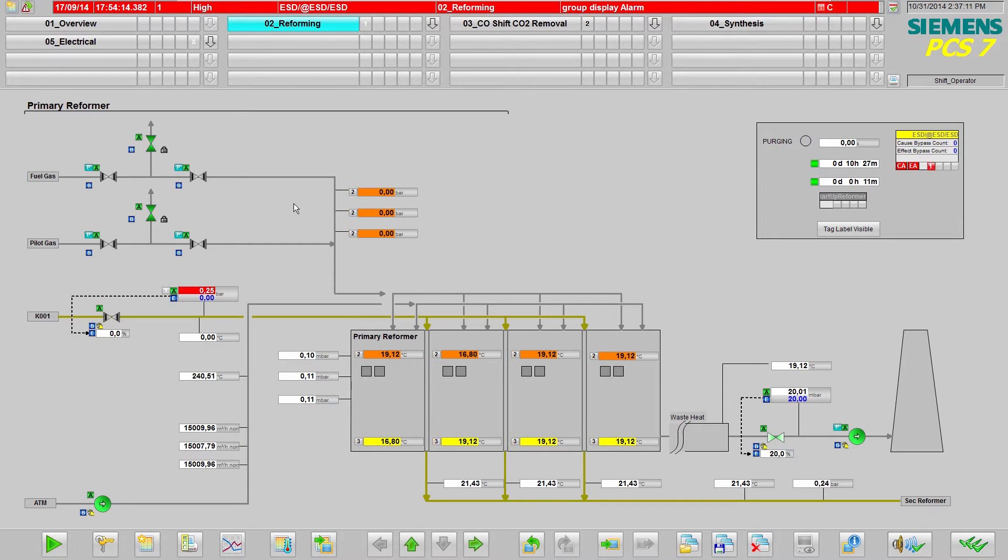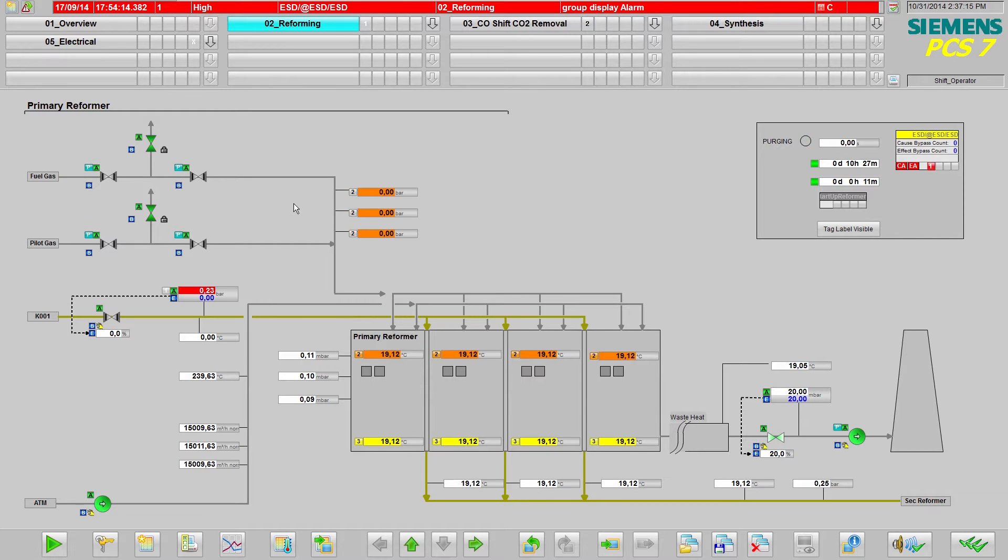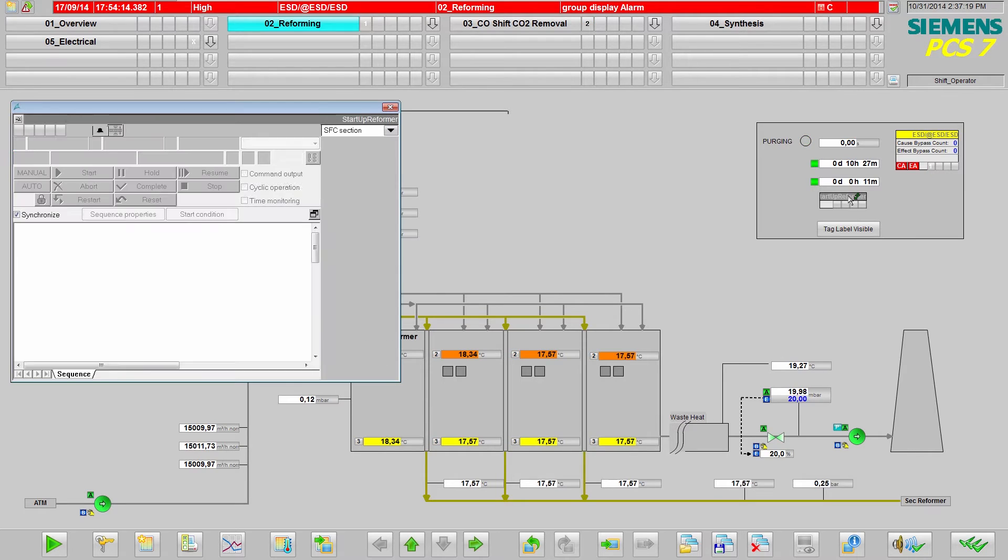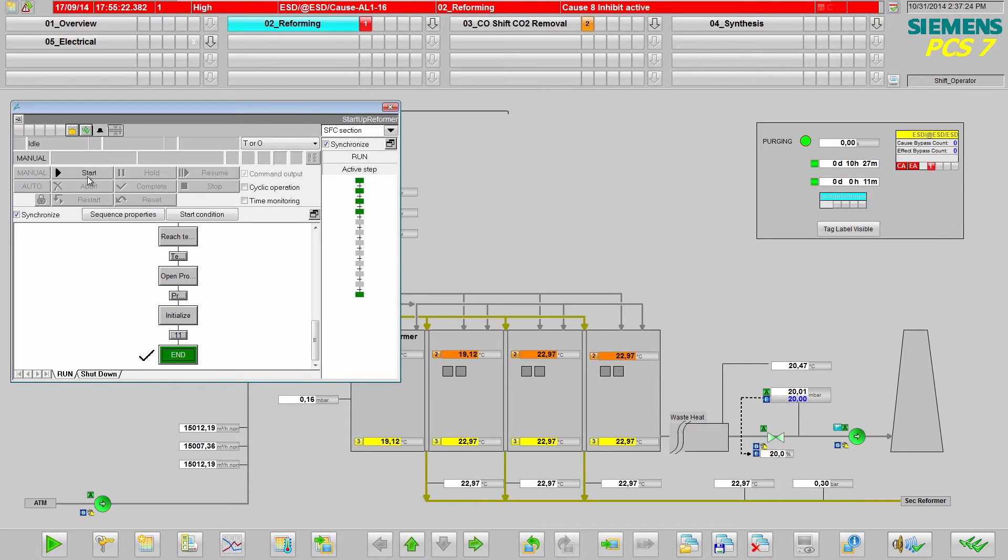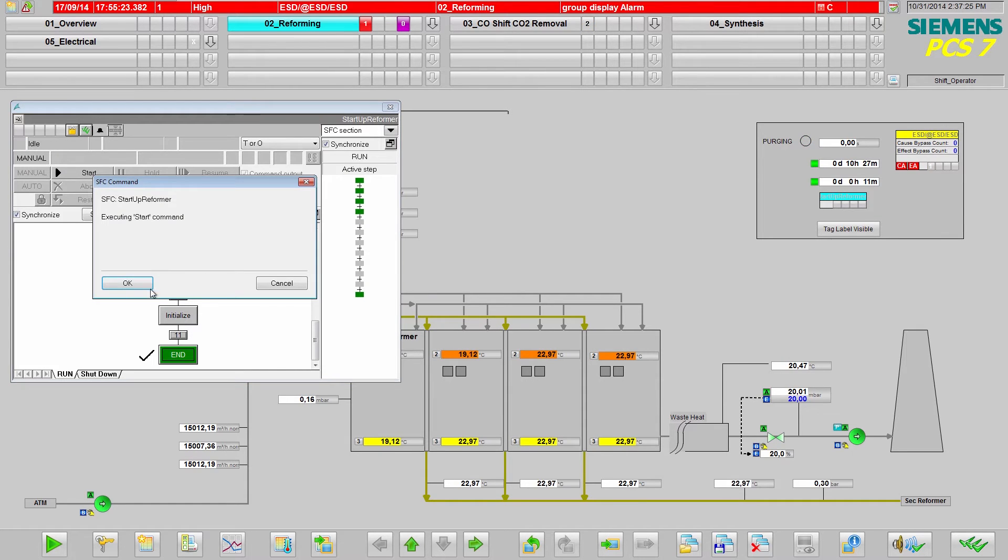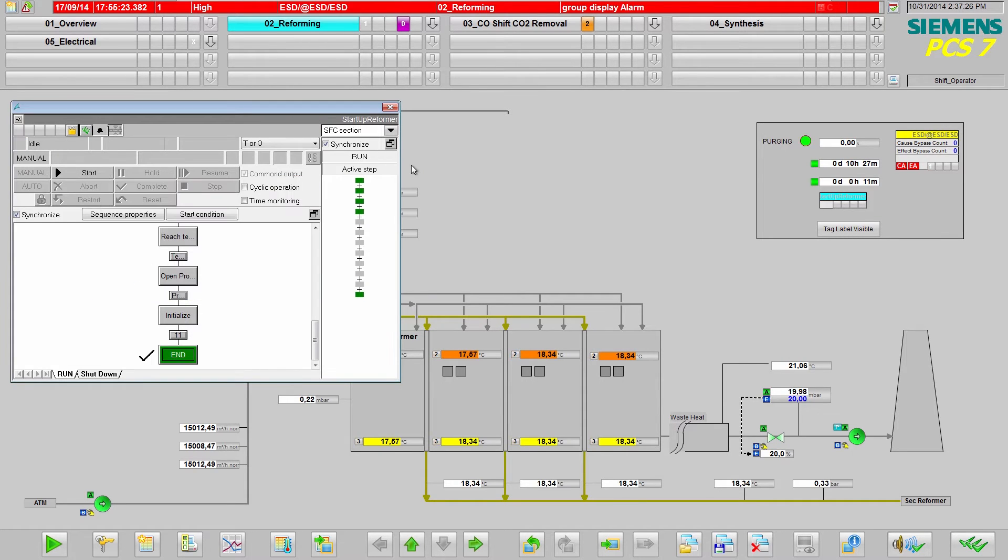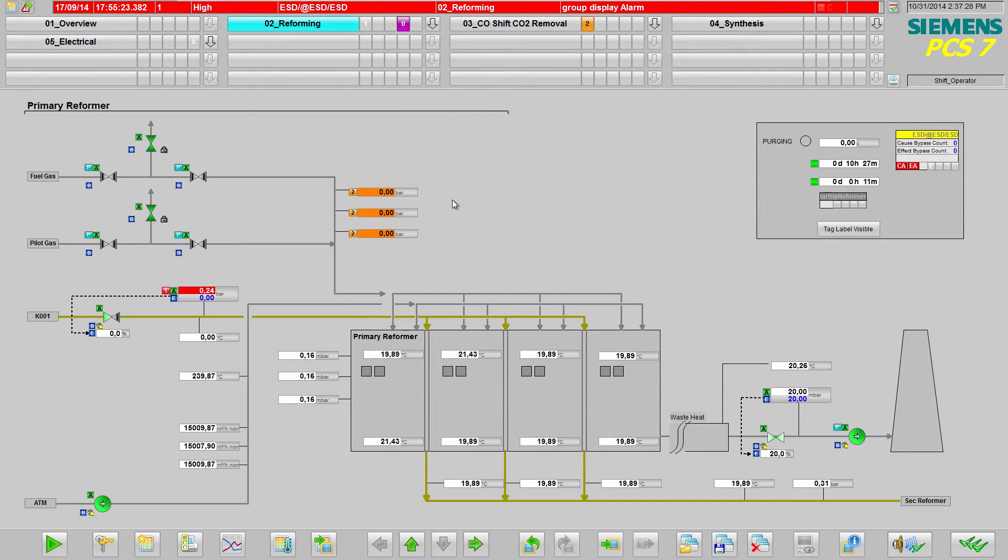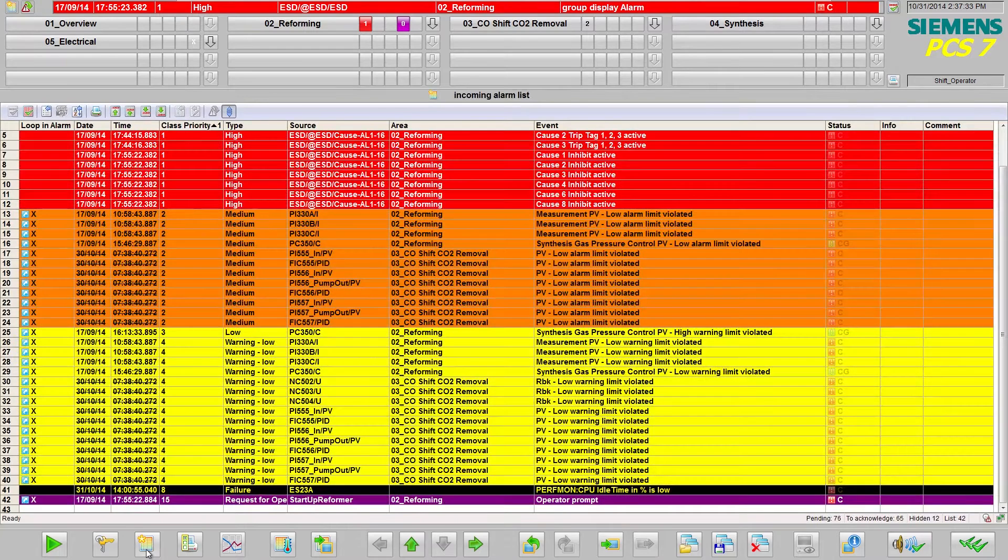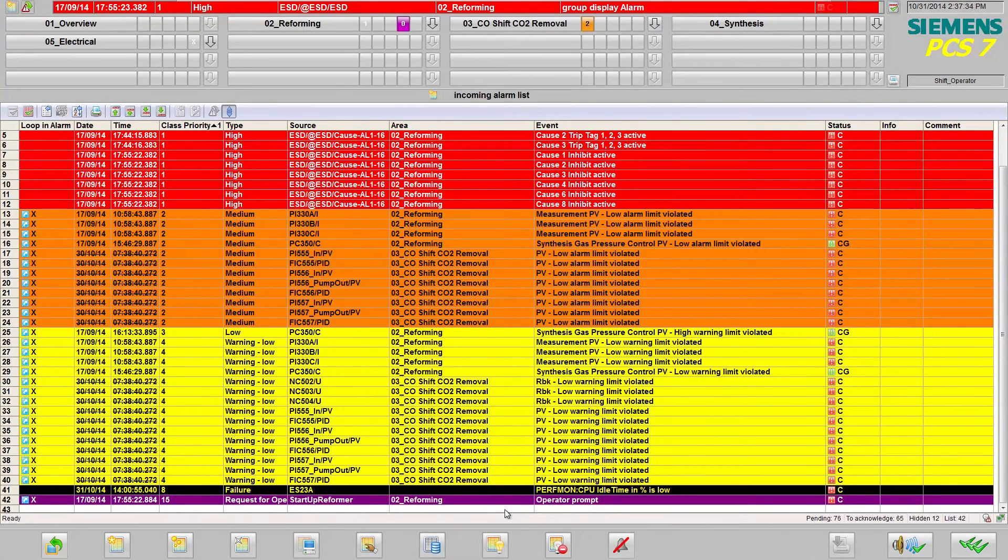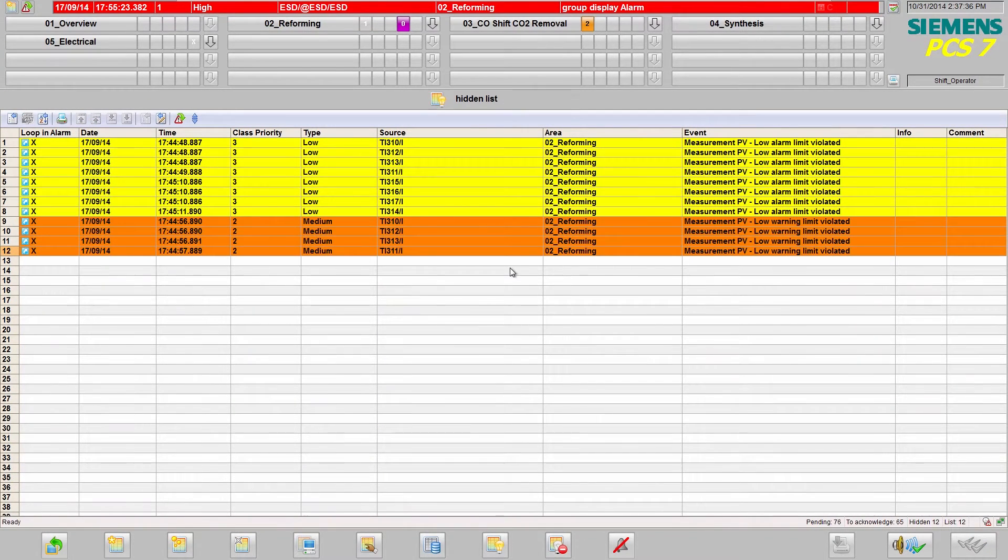Smart alarm hiding automatically suppresses them and helps the operator focus on the relevant alarms. To simulate the startup phase and generate the alarms, I am starting the startup sequence of the reformer. All alarms assigned to the reformer and plant state startup are displayed in the list of hidden messages when hiding is activated.